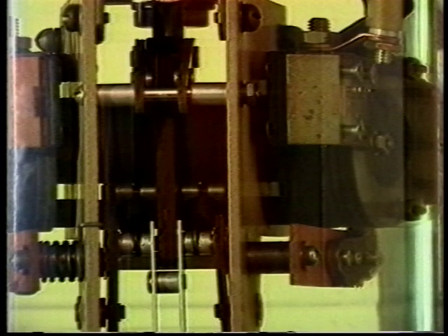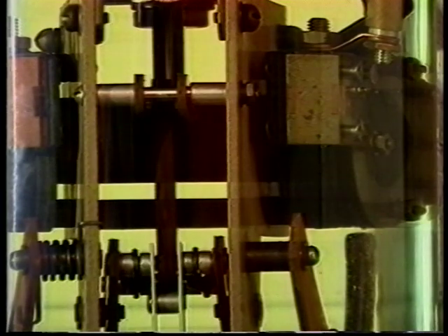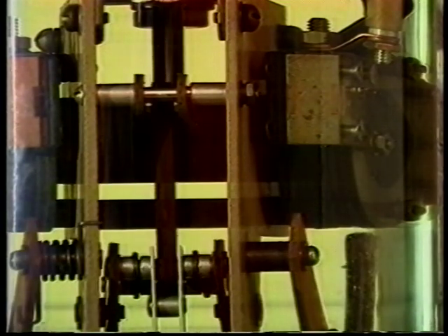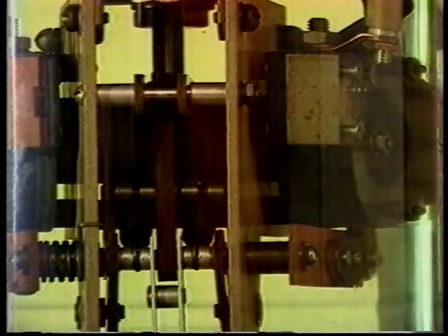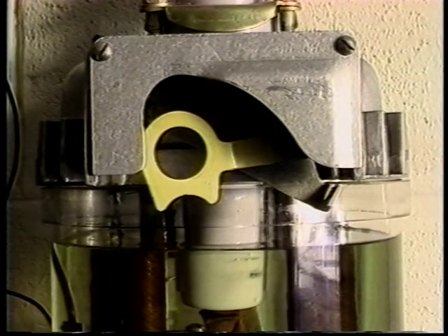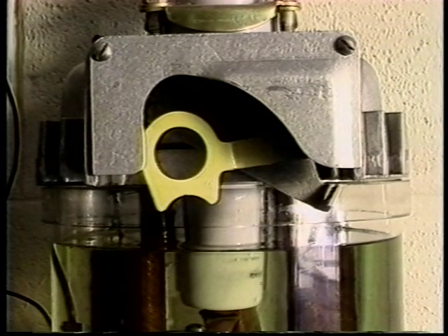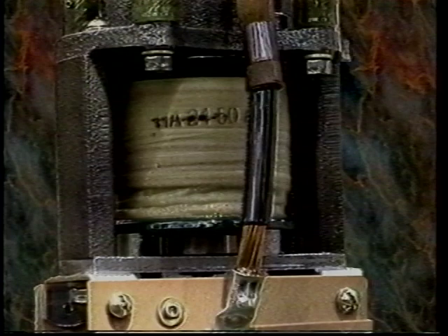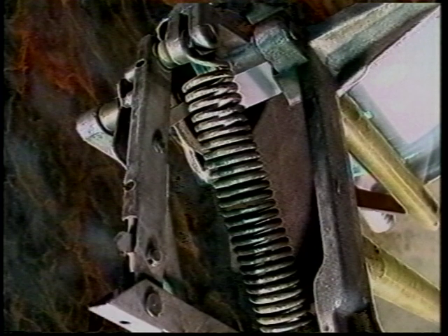or hold closed the main contacts. The tripping mechanism is the device that releases the holding means and opens the main contacts. In most cases, the opening force is furnished by springs that are charged by the closing mechanism. The closing mechanism is a solenoid coil, springs, or a motor and gear arrangement. The closing force serves to close the main contacts and at the same time charges the opening springs.